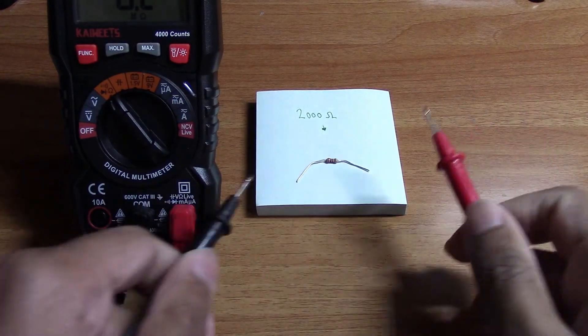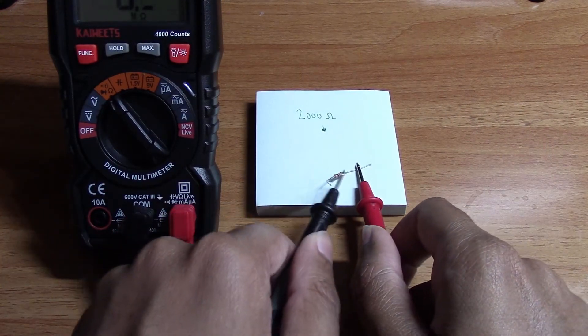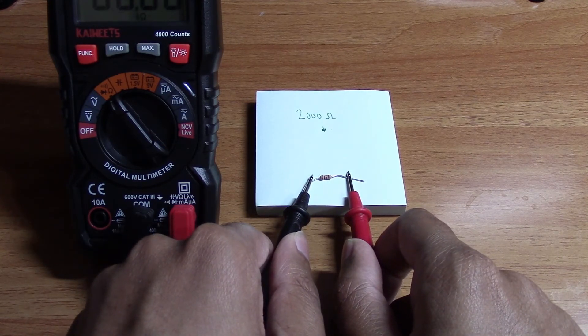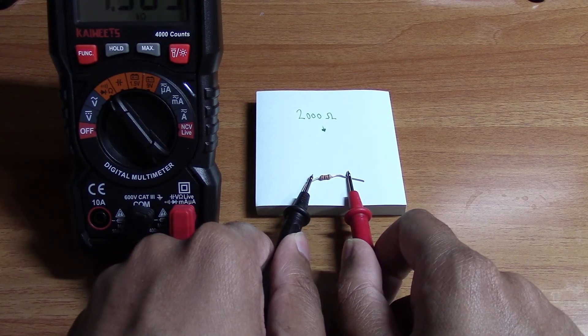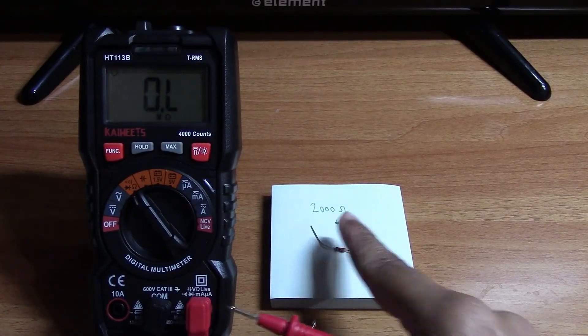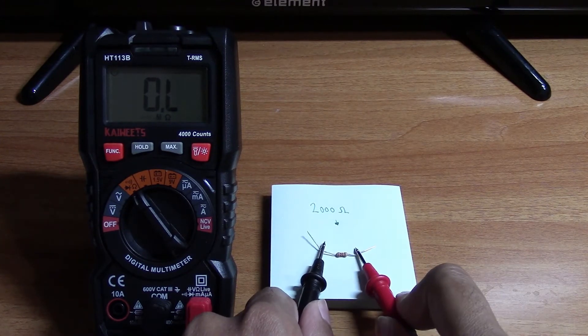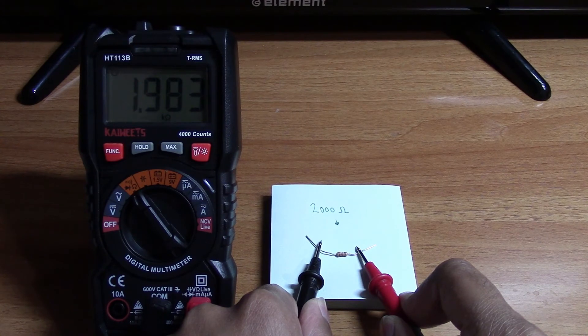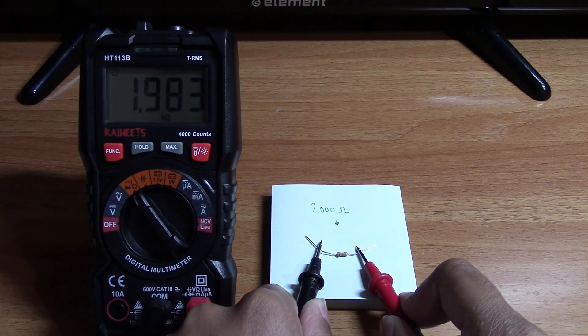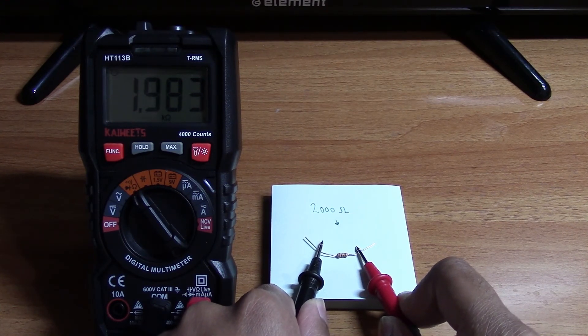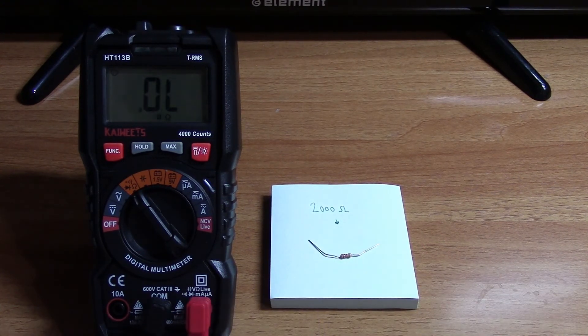Testing this, we just put one probe on one end and one on the other. Let's raise it up a little bit. We get 1.983, so that's going to be 1,983 ohms, which is right within range, so it's good.